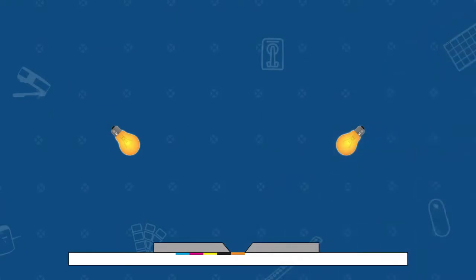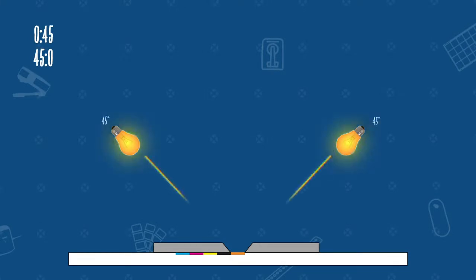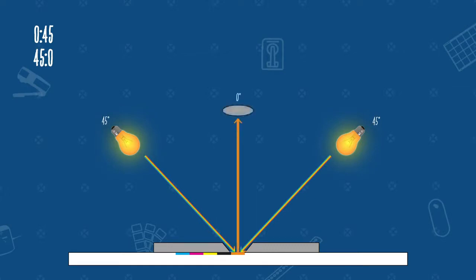One of the most common geometries is the 0/45 or 45/0. The 45/0 measurement geometry emits light at 45 degrees to the sample surface and measures light reflected at a fixed angle to the sample at zero degrees. This geometry excludes gloss to most closely replicate how the human eye sees color, and is commonly used for measuring color on flat, smooth, or matte surfaces.